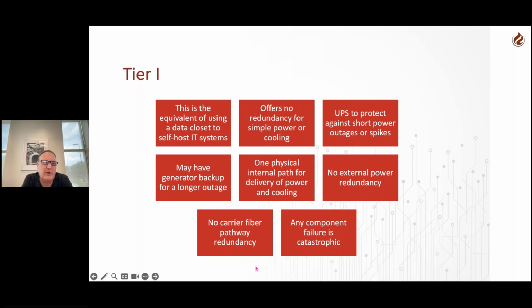They have all their equipment in a rack. They probably have an uninterruptible power supply, or UPS. However, in my experience of seeing a lot of these rooms, typically these UPSs aren't maintained well. They have batteries, the batteries go bad, and no one really keeps a good eye on these things, because at the end of the day, no one's responsible for it. And often these UPSs actually cause outages versus preventing them, so they can be an actual source of failure themselves.